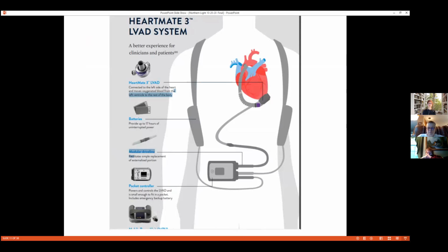This is just an outline of the basic equipment you might see with a patient who has an LVAD. So this part is internal, where the pump is in the person, and this is internal too. This is called the drive line. Some patients call it their lifeline, and I encourage them to call it that because that's what's running the pump, and if it gets damaged, the pump could stop. There is actually a modular drive line, which means there's a disconnect point here. If for some reason this part of the drive line got damaged and we needed to change it out, we wouldn't have to replace the whole pump.